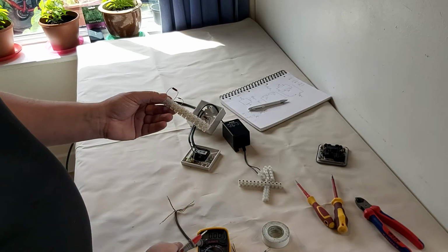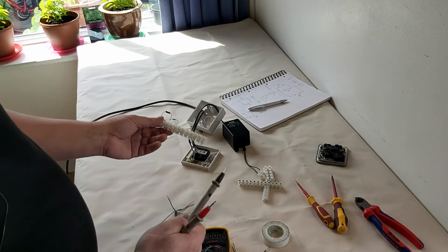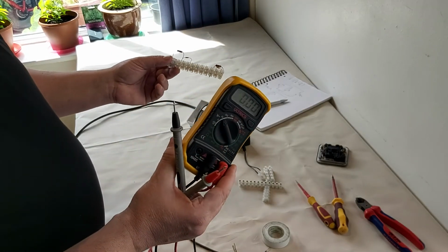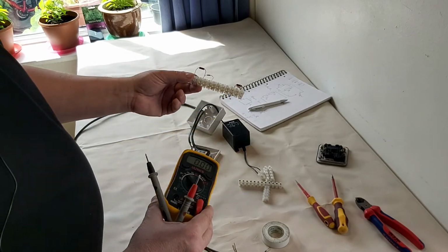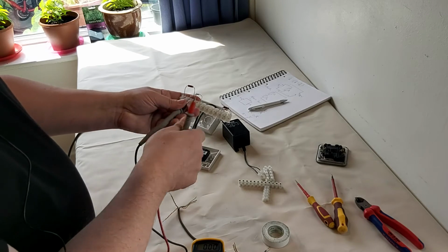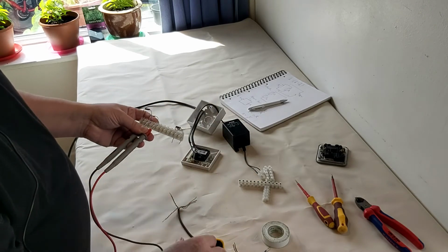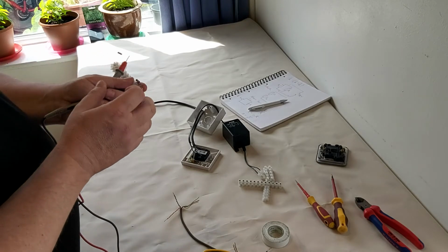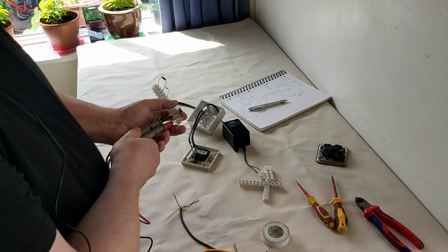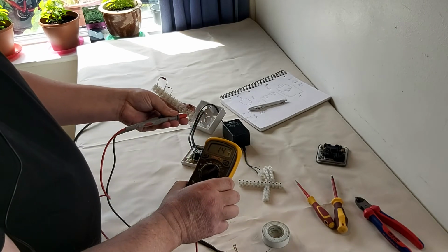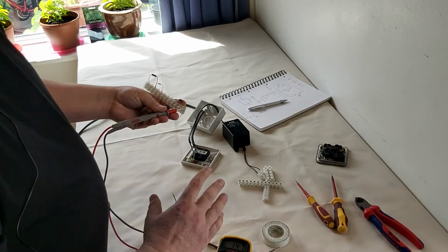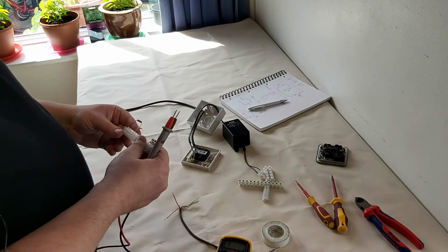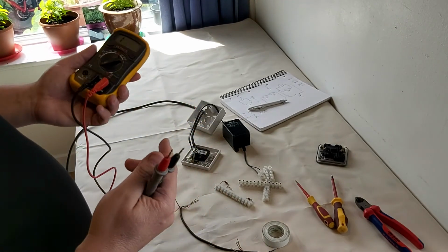power connected to that when you're doing that, because this will give you a wrong reading. Basically what this multimeter does, it sends a certain voltage to that resistor and measures the current which flows through that resistance. When you have this voltage connected to the resistor and you have some other voltage, you will get wrong readings. You will never get a proper measurement. So when measuring on different devices, be it alarm, intruder, fire, if you're measuring resistance, there shouldn't be any other voltage than the one from your multimeter. Otherwise, you won't get a proper value.